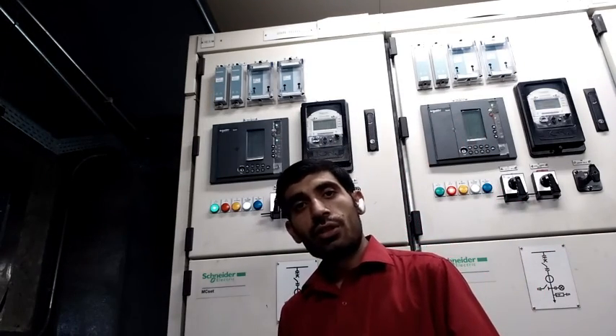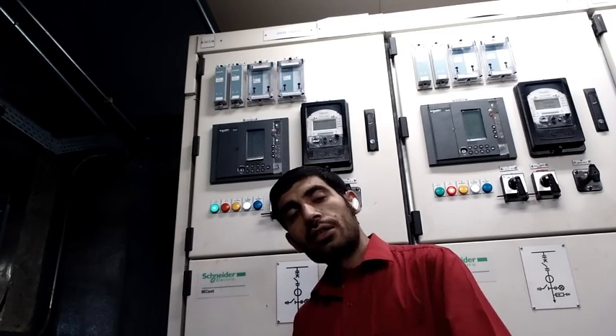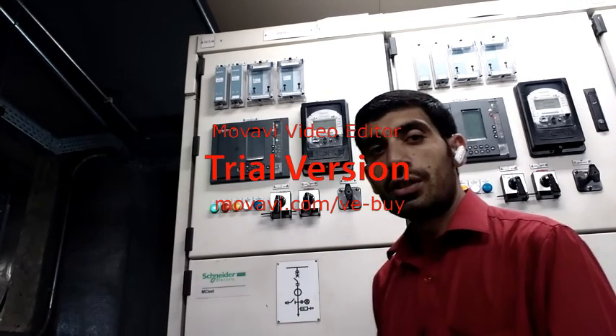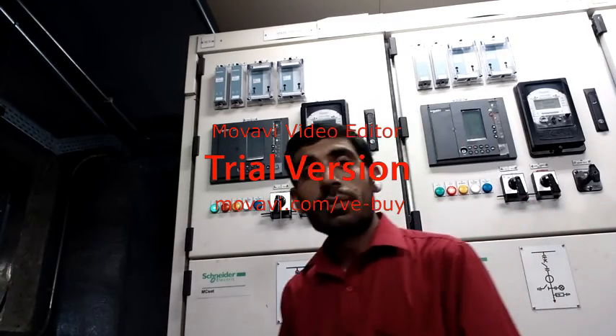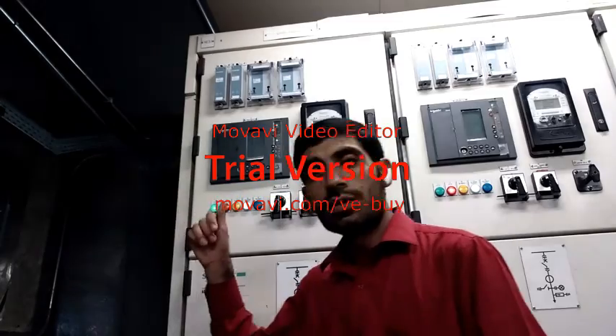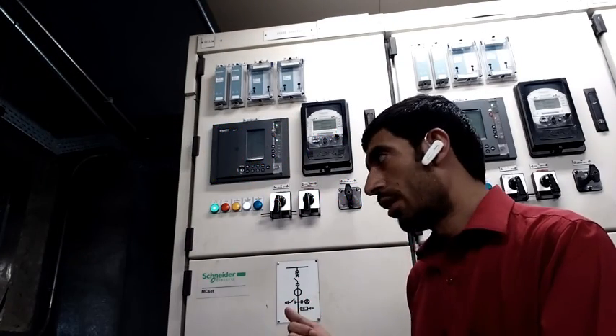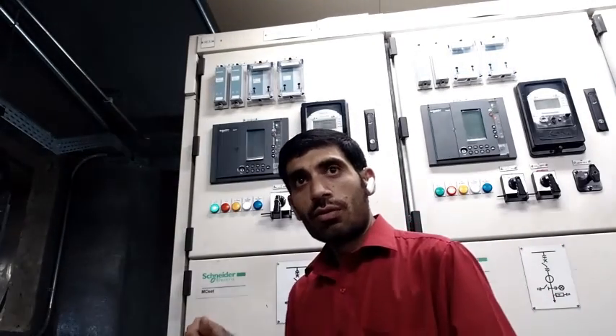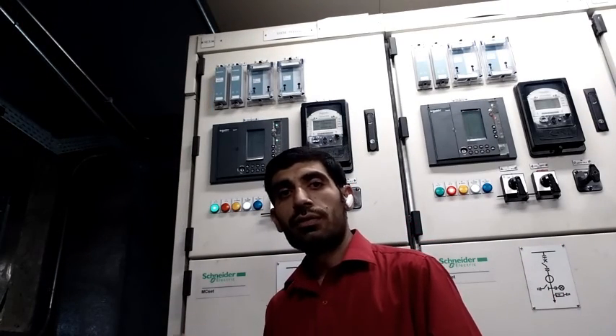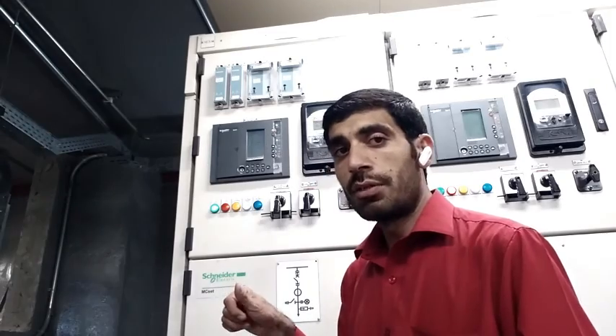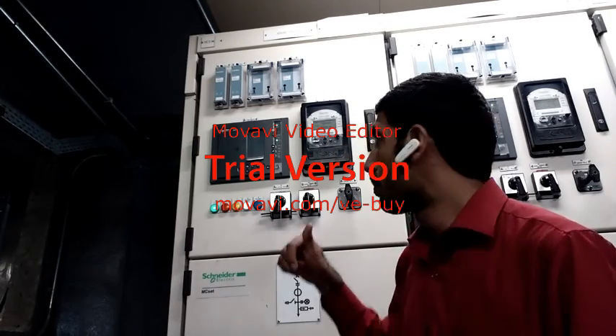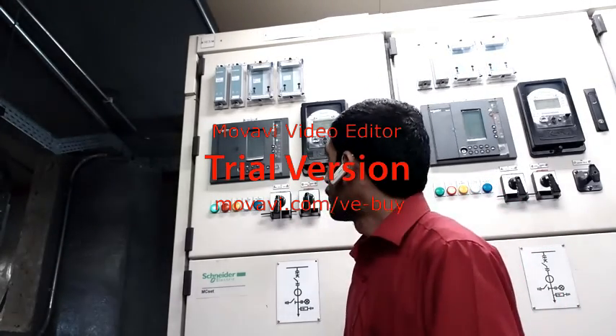Inject 0 voltage and increase slowly and check how much voltage it takes to pick up this relay. I think more than 70 volts is the pickup voltage of this relay, and the drop off voltage. When we want to check the drop off of this relay, we decrease the voltage slowly and check how much voltage it takes to drop off. And this will trip, I think less than 30 or 40 volts is the drop off voltage of this relay. And next, this multifunction meter.